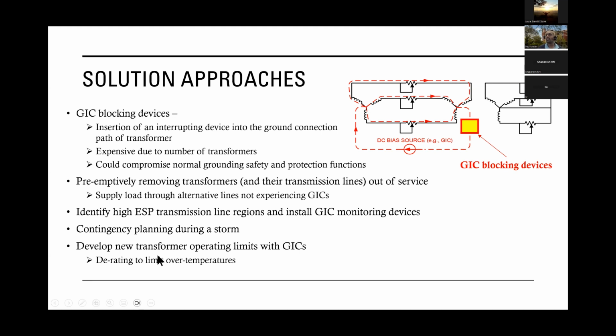The other thing is to look at transformer capability. If the GIC is not so severe, keep that transformer running even though there's GIC flow, as long as it can handle it without being taken out of service. There's a lot of work being done in the industry to decide on transformer operating limits with GICs. If there is a GIC in a transformer, lighten the load on it and readjust the system so the transformer doesn't get overloaded and fail.